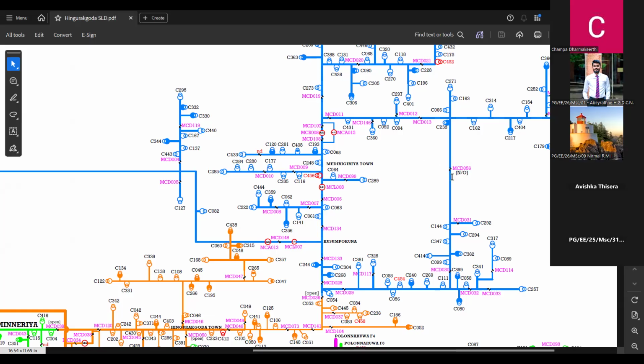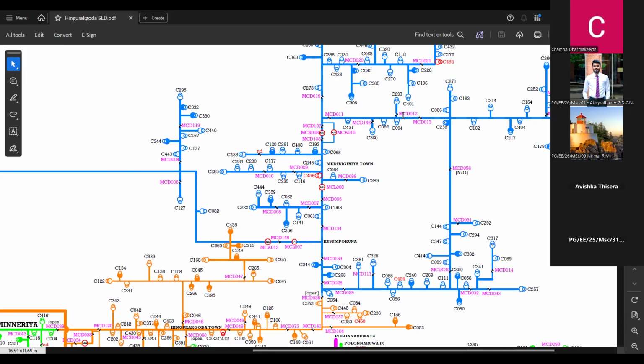So this is the normal operating point, but this normal operating point changes frequently due to maintenance. That means, say, for example, there's a maintenance in between these locations. So what we can do is switch off from here and switch off from here, isolate this section and carry out our maintenance. At that time, power up to this node is coming from this way up to here. Is it clear what I have explained to you?